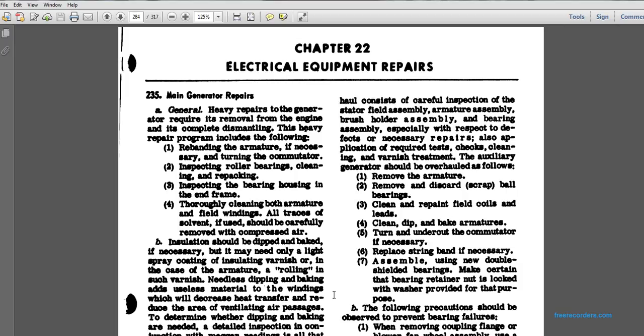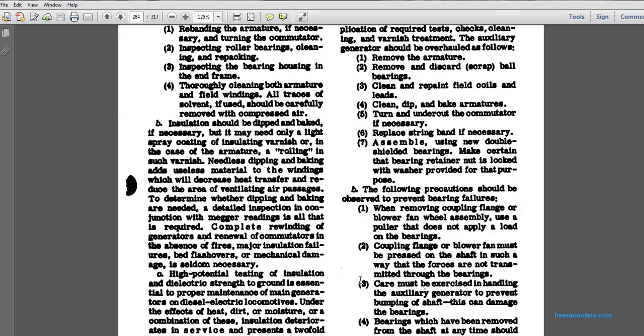Assemble using the new double shielded bearings. Make certain that the bearing retainer nut is locked with the washer provided for that purpose. The following precautions should be observed to prevent bearing failure. When removing the coupling flange, blower, or fan wheel assembly, use a puller that does not apply a load to the bearings.